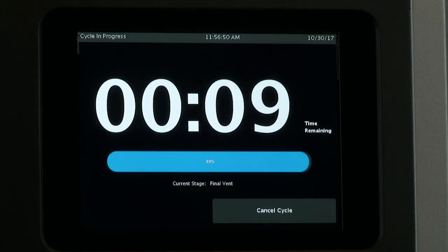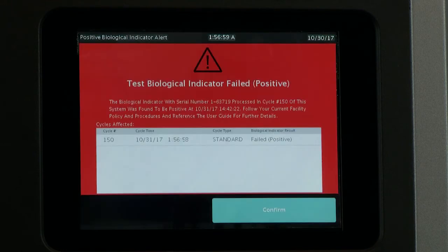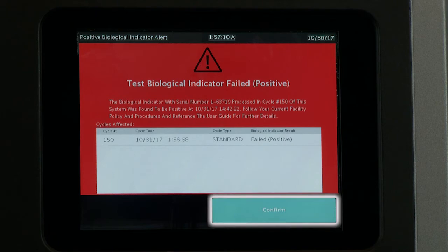Note that if the STERRAD Velocity Reader detects a positive test biological indicator when the sterilization cycle is running, the notification screen will only appear after the completion of the sterilization cycle. All known potential loads since the last negative test biological indicator result are listed on your screen. Touch the Confirm button on the screen to acknowledge the test BI used in the load has a positive result.